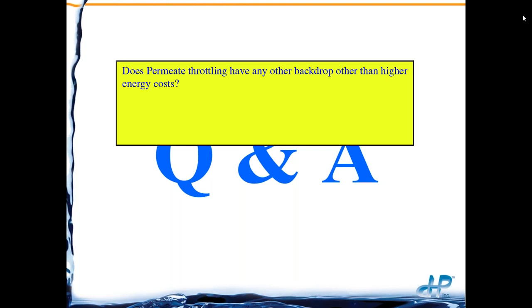Does permeate throttling have any other drawbacks other than higher energy costs? Other than the cost of the equipment itself, not really. If there's a lot of permeate back pressure — above 50 to 75 PSI — it may require changes to the permeate piping between the membrane and the valve. Also, unless the valve is automated, someone has to manually go out and change its position every time operating conditions change.